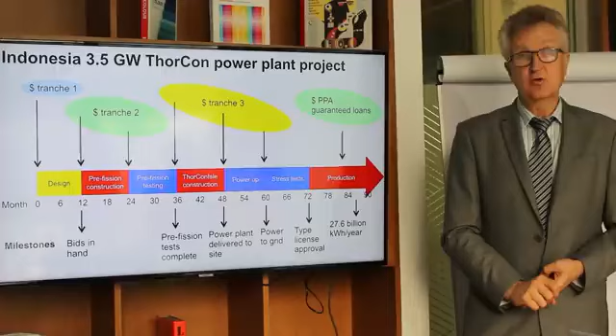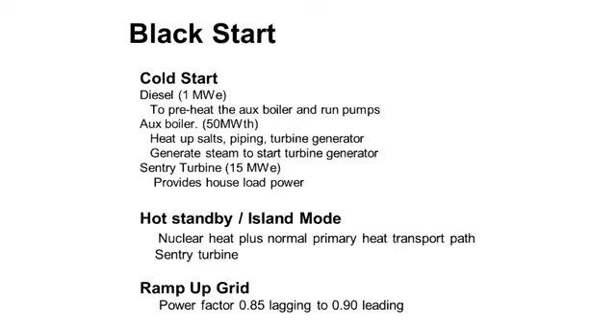It lets you respond quickly to changes in demand. If the plant was cold, like it would be when we first install a power plant, we use diesel, about 1 megawatt electric, to preheat the auxiliary boiler and run pumps. Then we use the aux boiler, about 50 megawatts thermal, to heat up the salts and the piping and the turbine generator, and generate some steam flow through the turbine.